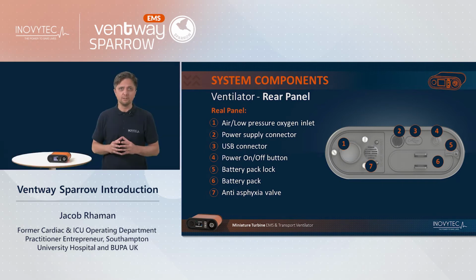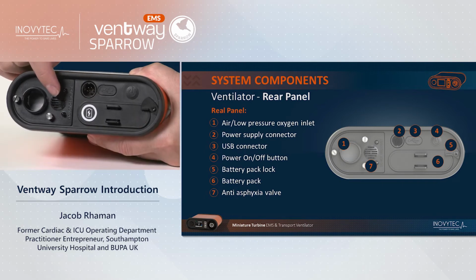And 7, finally coming back to the left-hand side of the ventilator, this is where the anti-asphyxia valve is located. This valve is used if either side of the patient circuit becomes blocked or occluded for any reason.